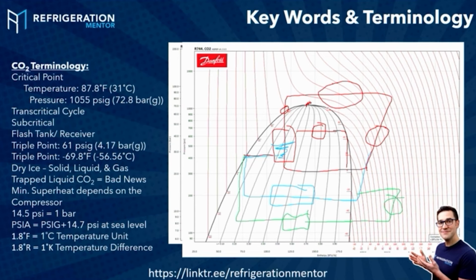And then you have your suction, you have your discharge, and then it comes back to the main manifold that goes back through the medium temp compressor. And this is why they're called transcritical booster systems. So you're taking this low temp discharge, it comes up to medium temp suction. We have this flash gas going to this medium temp suction, and then it all comes back here. So these medium temp compressors are really just taking all the refrigerant and compressing it, taking the heat out of the system, bringing it up to the condenser gas cooler where that is rejected to the planet. Hopefully they're doing some sort of heat recovery. And that's some of the main terms for sure.